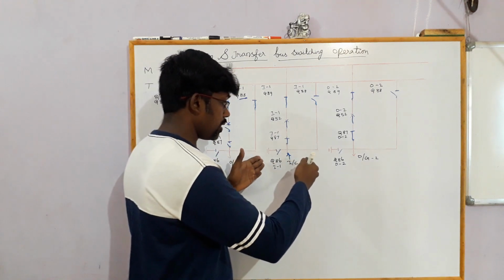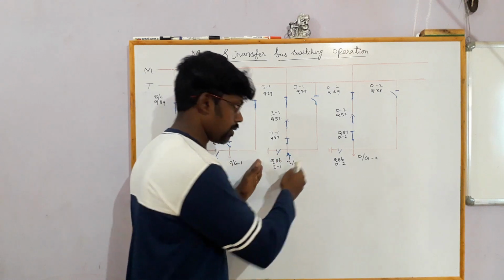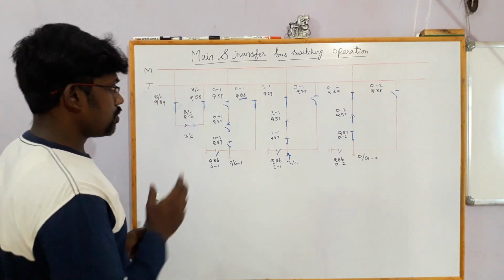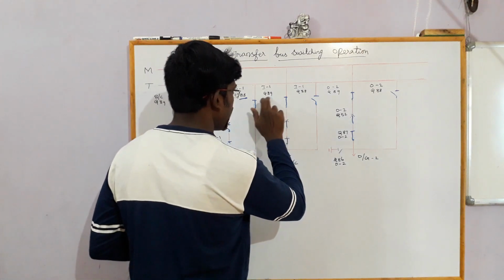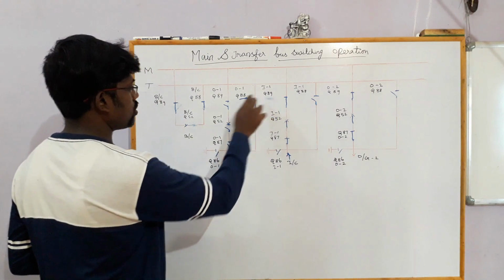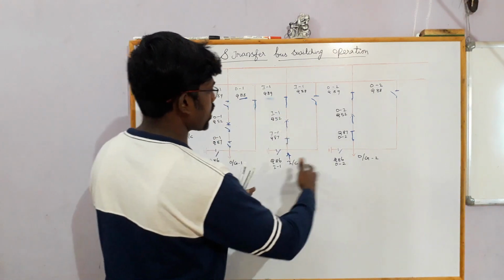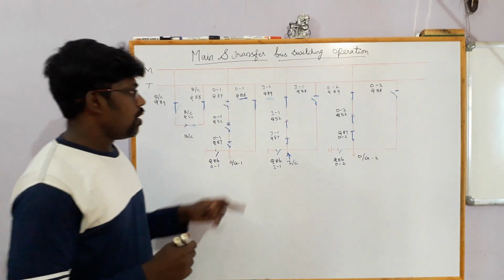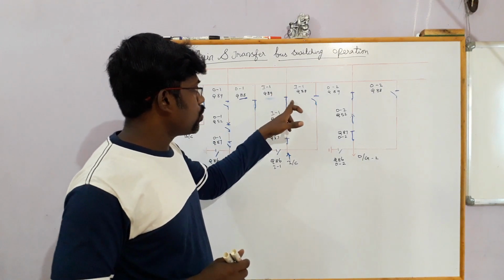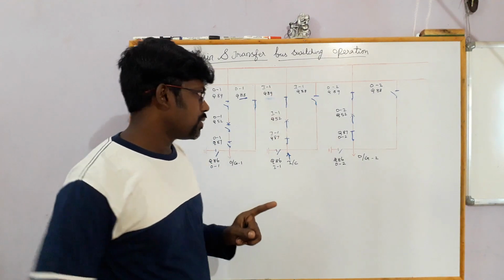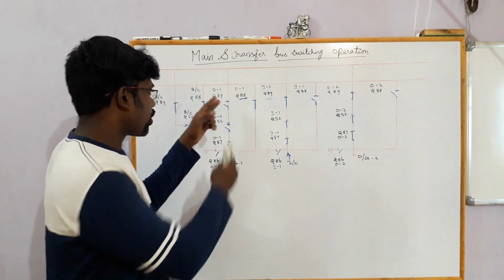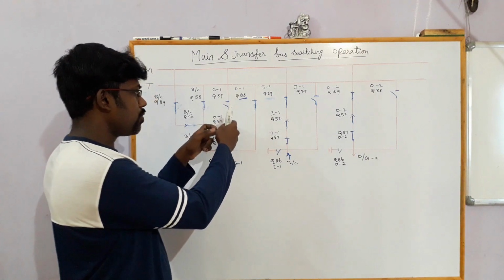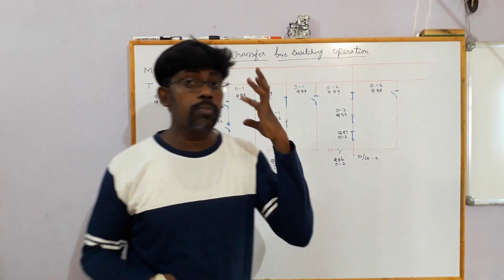First we are going to see the switching logic for the incomer. We are going to make a logic for this Q89. This Q89 logic is the same for all outgoing and incomer. Everything is the same. This Q89, even for the bus coupler, is the same. If you are going to close this Q89, what is the normal sequence? We will close this Q89, then only we will close the breaker. That means the breaker should be in open position.